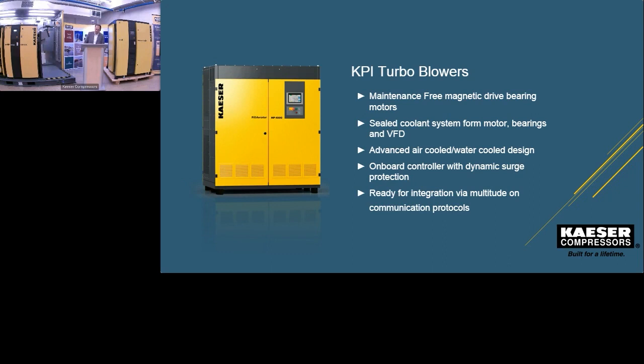Another unique aspect of this, it has an active magnetic bearing control system. So we're not the only ones out there who have magnetic bearings or active magnetic bearing control, but our KAESER turbo blower has this. Something which is unique to it is that it does not require battery backup. So of course, those magnetic bearings have a host of sensors in there, which are monitoring the shaft position, fluctuations up and down, as you speed it up and down. Those sensors are monitoring the shaft position and adjusting the magnetic field to hold it in place.